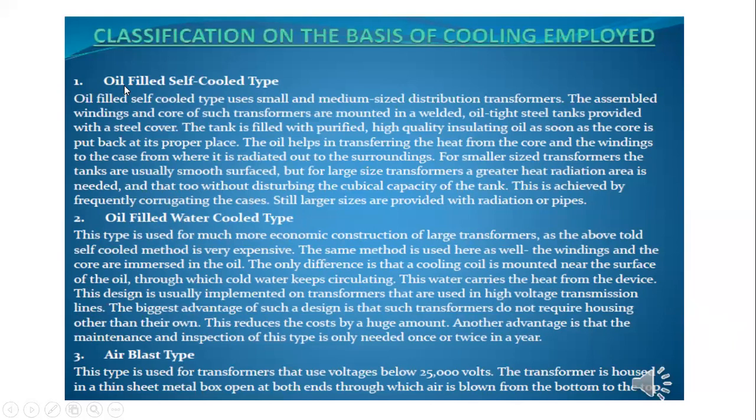What is the difference between the oil-filled self-cooled and oil-filled water-cooled types? In that case, we are using water, and that water carries the heat from the device. The cooling coil is mounted near the surface of the oil, through which the cold water keeps circulating. Therefore this reduces the cost by a huge amount by using that water.